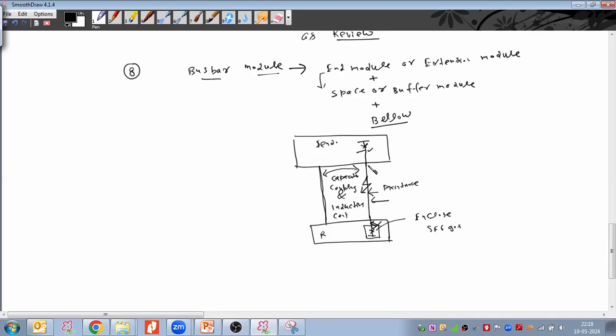So it means even though this line breaker is open and the line is isolated, the charge will exist on this conductor. So when you are going for maintenance, then you are closing the earthing switch, right? Here space is not available, so I'm taking it outside. So what will happen when your moving contact is approaching your fixed contact? What will happen? Your contact has the charge.